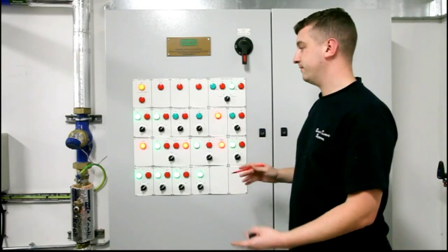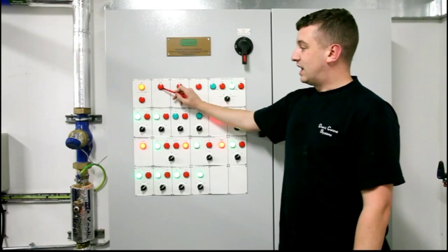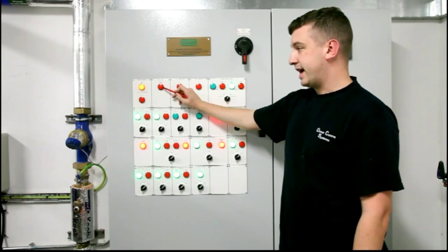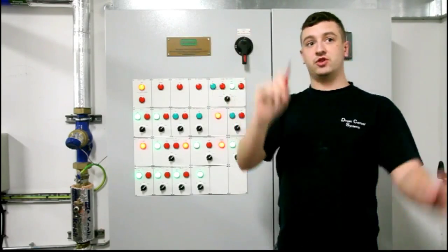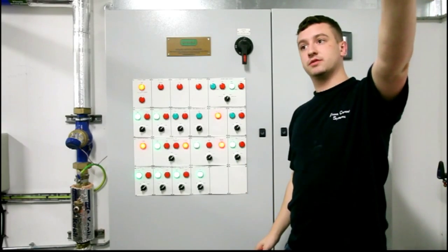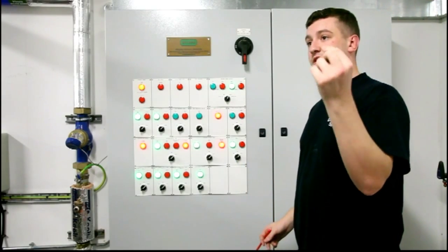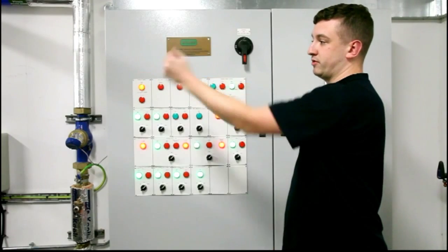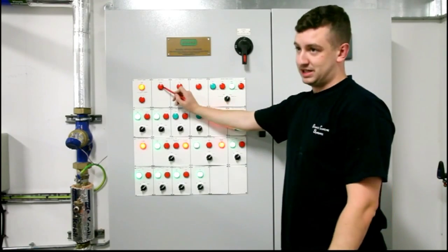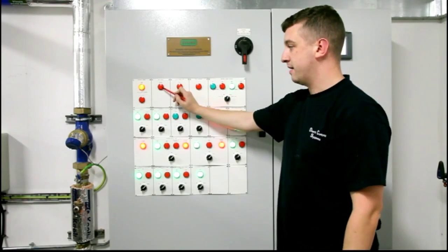all of the plant. We've got the gas valve closed, which operates if there's two thermal links above the boilers. If either of them are obviously burnt, or if someone presses that knock-off button, it automatically closes the gas valve.